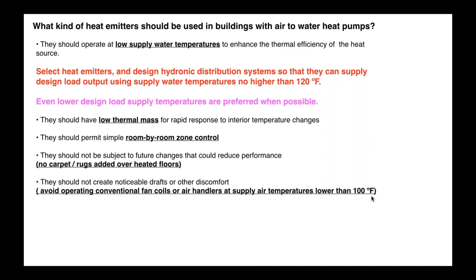And obviously, it's a good number if you're using a ModCon boiler. Or if you're perhaps today, maybe a building's going with a boiler with the idea that 5 years from now, 10 years from now, maybe a heat pump will be the replacement for that boiler. So I want to design the distribution system to at least be compatible with what that future heat source might be. So I'd like the idea, especially if you're dealing with buildings that have low loads, you want to have low thermal mass for relatively rapid response.